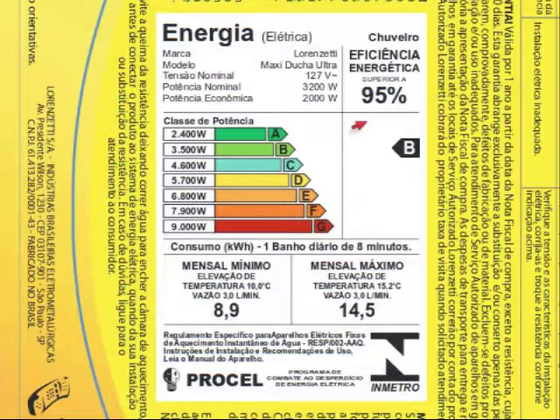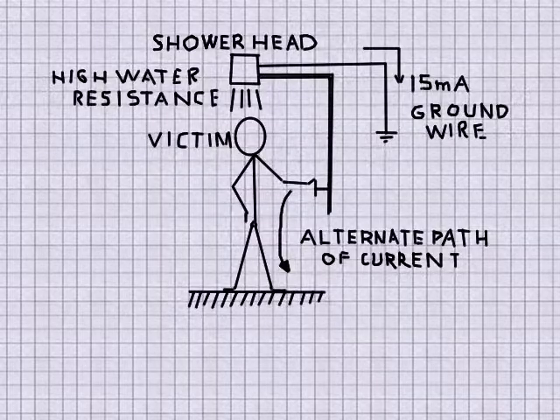These electric shower heads are efficient. They have been certified to achieve a 95% efficiency according to the Metrology Institute. In today's quest for a low-carbon footprint, such an efficiency is indispensable. It is a very affordable solution for places where water does not have to be heated much above ambient temperature. On the other hand, when it comes to electrical safety, it seems to me that the reliance on the ground wire connection and the water resistance is a little precarious.